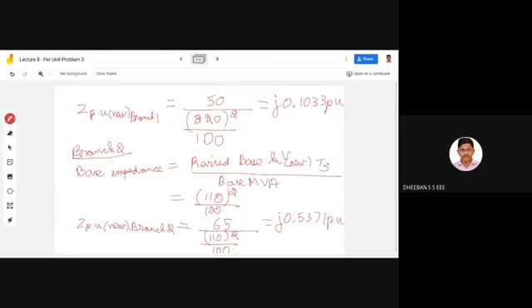Okay, so this is with respect to the second branch. Finally we'll be moving towards the load, which is your motor. For the motor, Z per unit will be equal to 0.2. Base MVA is 100, the given MVA is 70, and the voltage will be, so for here the voltage you have to consider is the revised voltage.